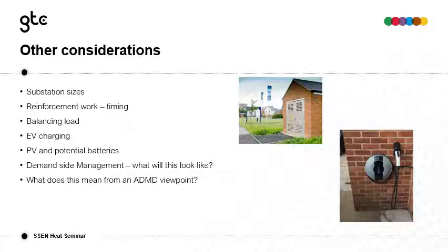Consider things like reinforcement that might be needed and the timing of that, so talking to the DNO and making sure they understand your phasing. As you build out, the ultimate path is from an LV supply, moving through an 11kV substation, and then onto a primary, making sure you're not building the primary on day one, and allowing the DNO to manage their capacity as much as the IDNO as well.